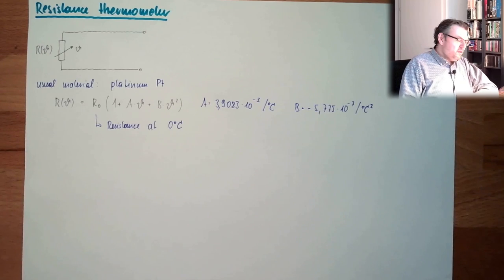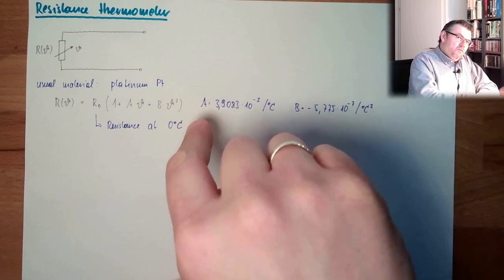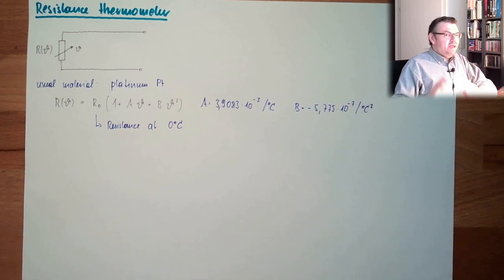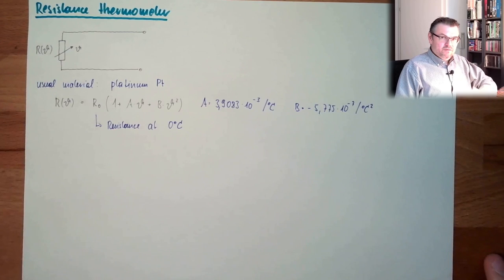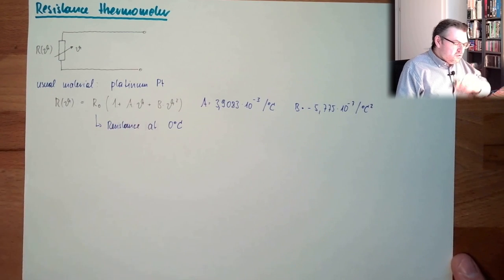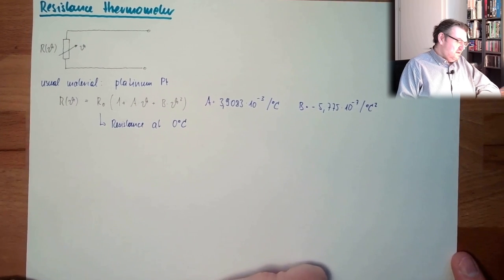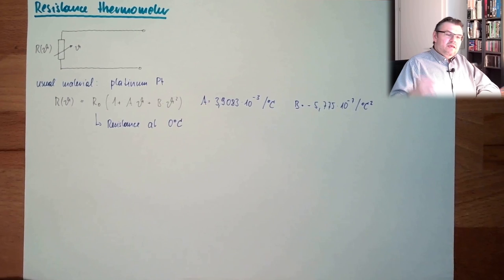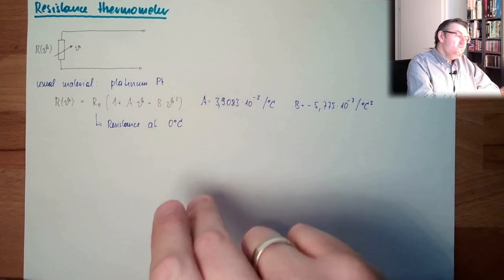Former times also nickel was used. But however, nickel you need, you know, raised by the power of 3, 4, and 5, and so on. And then you have a small window. It's by far not that linear like platinum. So, you need by far more of those factors. And this does not make it easier. And also, at areas below 0 degrees Celsius, nickel had some issues. So, nowadays, the usual material for measurement purposes is platinum.